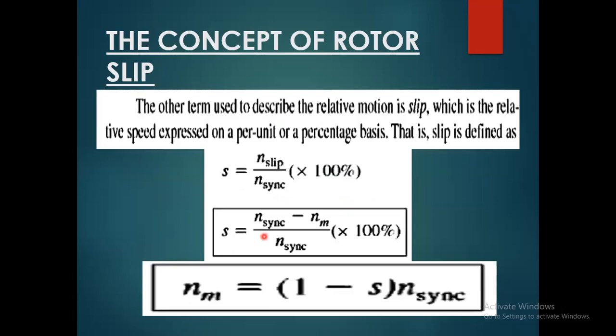Further continuing the session on the concept of rotor slip. The other term used to describe the relative motion is slip, and slip plays an important role in the rotation of the rotor in the field winding of the stator, which is the relative speed expressed on a per unit or percentage basis. That is, slip, represented by S, is equal to the slip speed divided by the synchronous speed multiplied by 100. By this formula we extract the value of slip, represented by S. Another formula to find the value of slip is synchronous speed minus mechanical speed, divided by the synchronous speed, multiplied by 100.